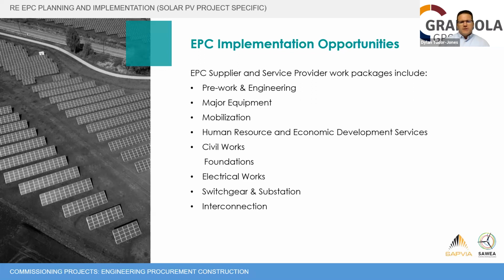The electrical contractor handles typical electrical work which takes place within the field, including the supply of components and cabling. Very important, I'm going to stress this, is lightning protection and earthing. A lot of the early stage round 1 and 2 solar projects have had consequential issues when lightning is involved, and it's taken out inverters, it's taken out communications, and they've had to do remedial work to try and fix it. So it's very important to do that planning up front, because it could be an oversight.